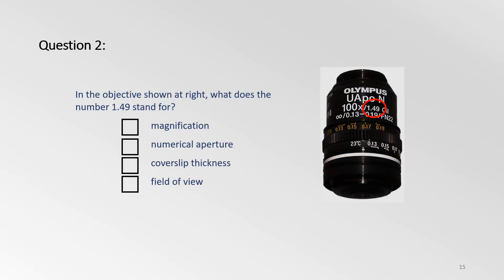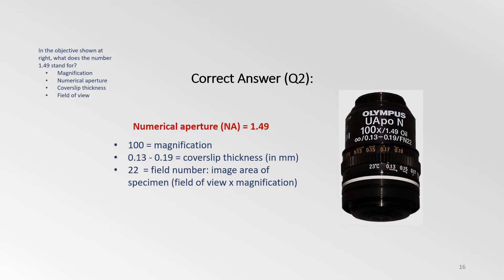Let's try another question. In the objective shown, what does the number 1.49 stand for? Magnification, numerical aperture, coverslip thickness, or field of view? 1.49 is the numerical aperture of the objective. 100 is the magnification. 0.13 to 0.19 is the range of coverslip thicknesses that are suitable for the objective. 22 is called the field number, which defines the image area of the specimen.